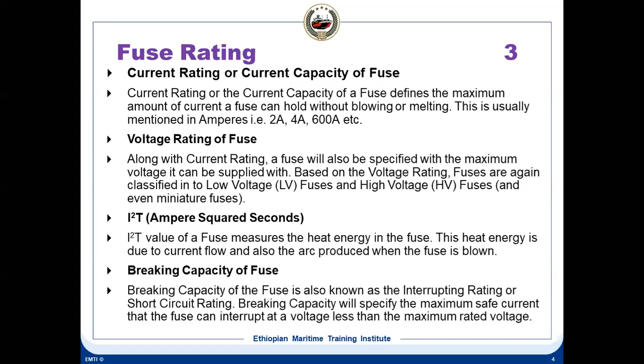The breaking capacity of the fuse is known as the interruption rating or short circuit rating. Breaking capacity specifies the maximum safe current that the fuse can interrupt at a voltage less than the maximum rated voltage. Okay.